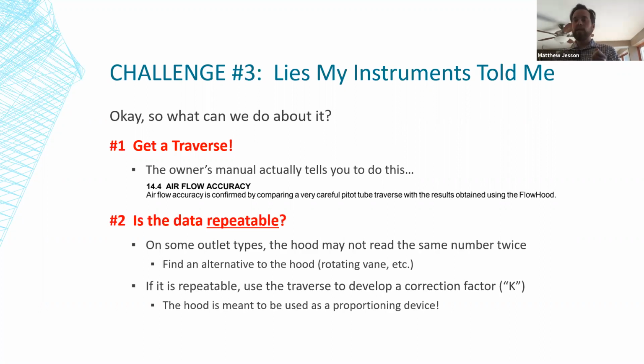I've tested this out where I would take the hood and put it up to that eyeball diffuser, hit the button, take the hood down just to look at the meter to see what that number is, then put it back up and try to get it positioned just the same way, hit the button again and get a very different number. When that's the case, you just can't use the hood. I can tell you that using the hood on eyeball diffusers and on most drum louvers is just not going to get you a consistent result, and you need to find a different way to do it. So find an alternative, the rotating vane, the bell grid, something like that. A duct traverse is always good if you can get individual traverses on the outlets. In the case of the eyeball diffusers and this test that I did, I ended up finding that the rotating vane actually read very accurately on them. You just put it right there in that opening. Those particular eyeball diffusers were sized just right for that too, I should say. The rotating vane fit right in it.